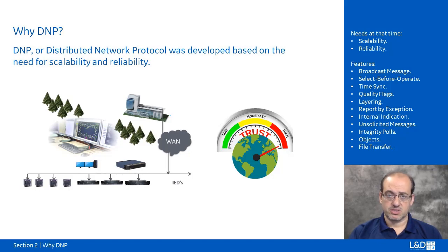An unsolicited message is what we call peer-to-peer communication, where a device will send information even though that information was not requested, as a result of an event or a change in data that the device has been programmed to report to the other device or to the master. So this opened the way for other open protocols to start implementing something similar to an unsolicited message.